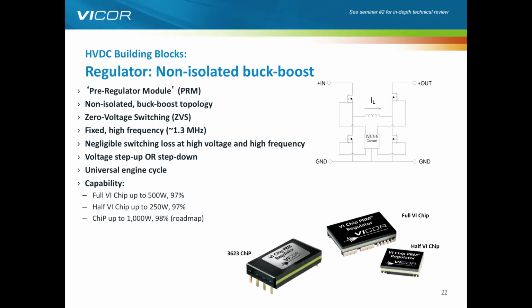And the combination of switching of those different MOSFETs, either single MOSFETs or paralleled MOSFETs, depending on the power output of the device, go from the buck to the boost or a buck-boost kind of function. A few things to note about this. The first is it's completely zero voltage switching, which means we can run at a very high frequency, which means we can reduce the size of the magnetics, which reduces the size of parasitics, which improves the efficiency once again. So we have this positive spiral of design.